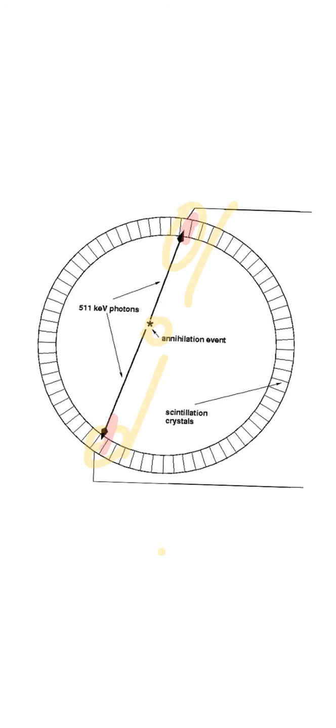The shorter your coincidence timing window, the fewer overall counts you will get, but that also can degrade your image. So the longer your coincidence timing window, the opposite is true. The more counts you'll collect, and in the image the resolution might be better, but in turn, you'll have more scatters and random events collected also.